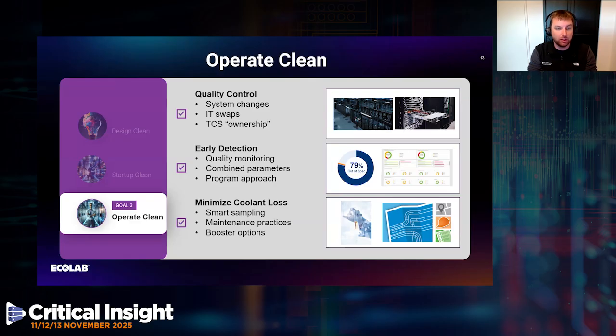It's important to also minimize the coolant loss, not just from an economic perspective, but what we also often see is facilities that have environmental constraints because of the substances used within the coolant. You need to have a smart sampling plan there. You need to have good maintenance practice and also the options to boost. And what do I mean by boosters? What we often see, for example, is that anti-corrosion inhibitors are being depleted over time by the system, especially when you have new systems or you have systems where there are a lot of IT swaps and changes, that some parts of these coolant inhibitors just run out. The same thing can happen with the biocidal chemistries used, that you run out of sufficient strength of biocide. And you need to be in time to prevent issues from happening there. The earlier you are, the better it is, the more problems you can prevent. So these are important things to consider when in operation.